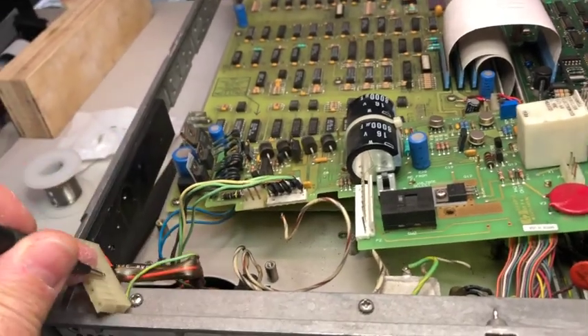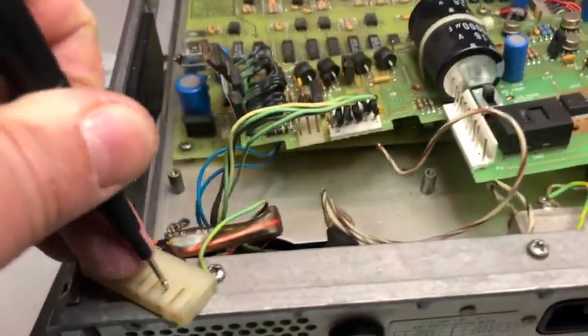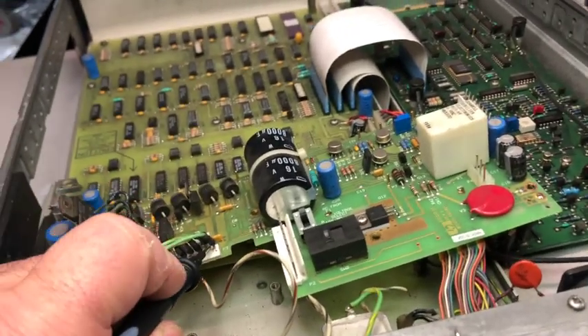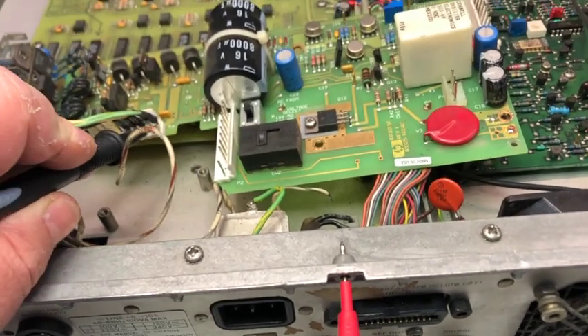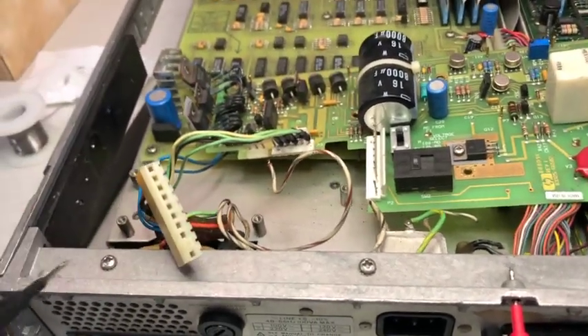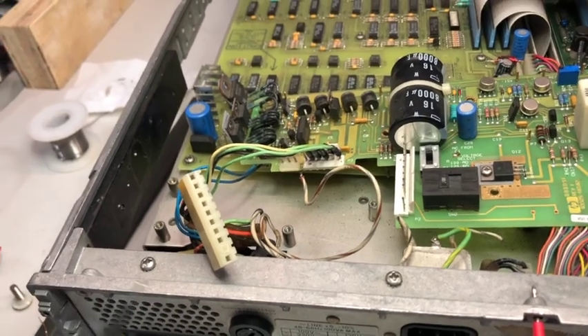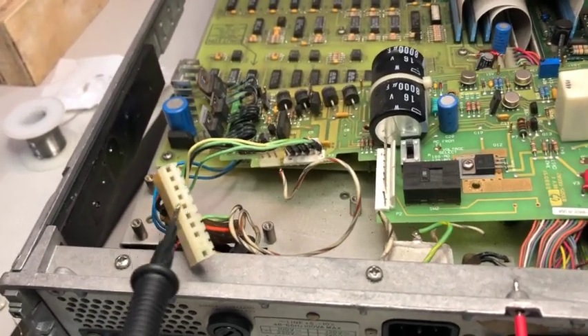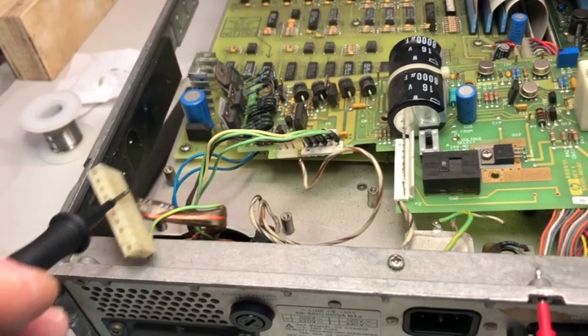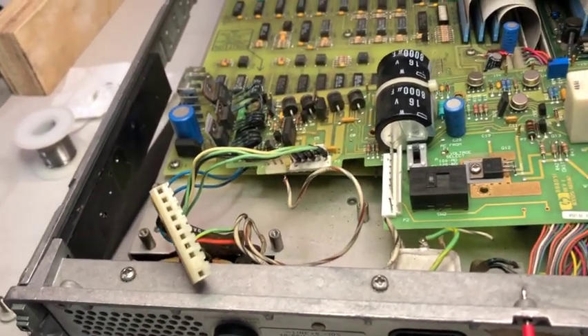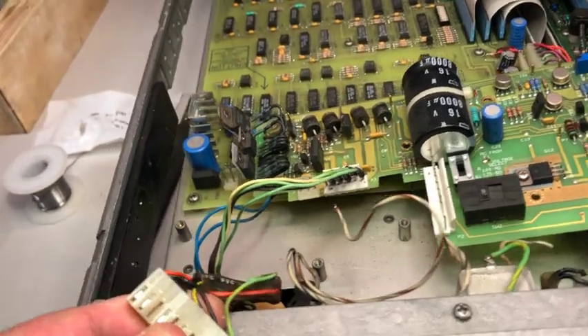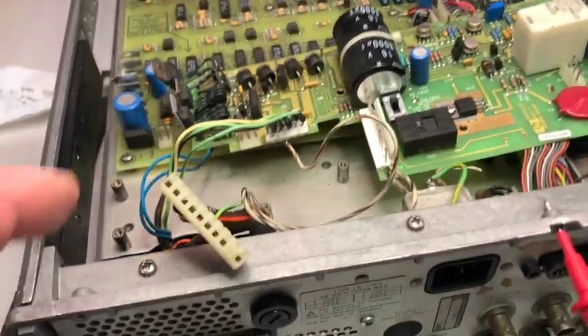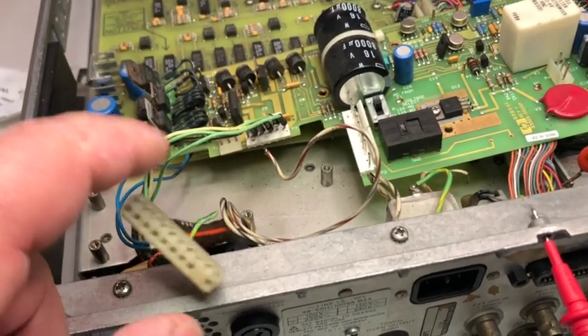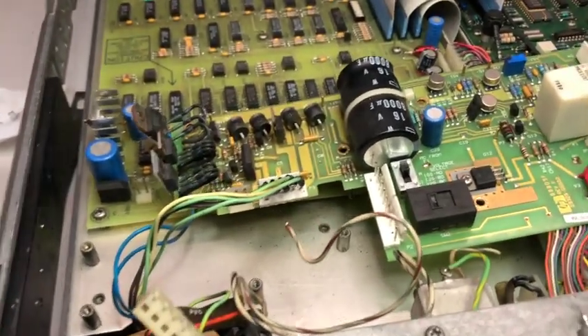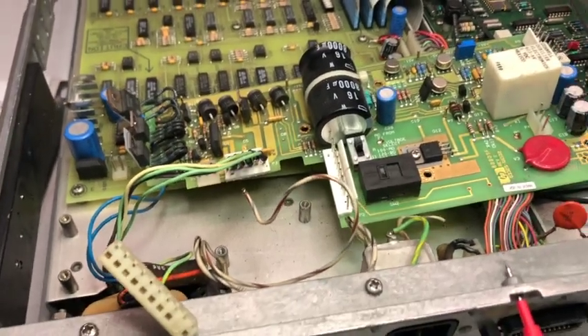Well, luckily, neither the primary nor the secondary section of the transformer has leakage versus ground. So at least we don't have a completely blown out winding. However, this doesn't mean that the transformer is still good, since it might be shorted between some sections on the primary, the secondary, or both.